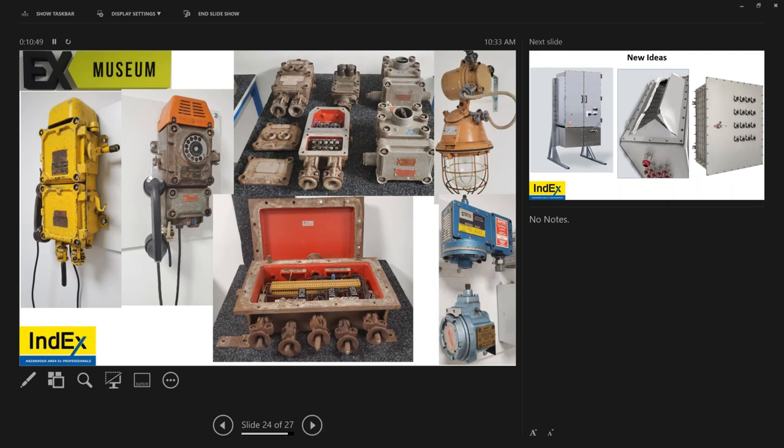Thought you might explain pressure piling. Okay, pressure piling is an internal explosion. When it happens, the pressure wave bounces off a solid surface and bounces back at even greater pressure. As it bounces back and forth inside, it has more energy, and it will crack the EXD enclosure if it didn't have a flame path. The flame path allows the release of that explosion in a controlled means.